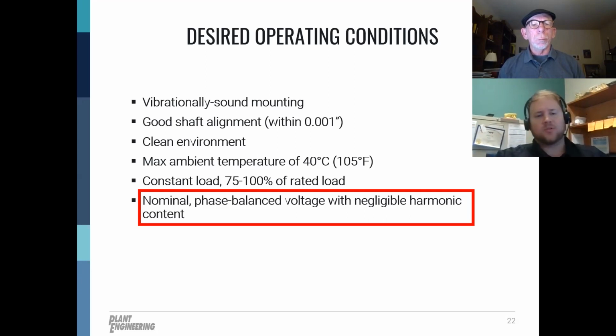So we talked about ideal voltage. Second, more of a mechanical issue, the motor should be aligned to the load to have as little mechanical vibration as possible. So, how do you do this? That's by shaft alignment. You have various tools out there. A very experienced technician is going to have done a lot of shaft alignments, so they will have some tools, but having a laser alignment tool may be a good addition to your toolbox, especially if you are doing a lot of these installations in-house.